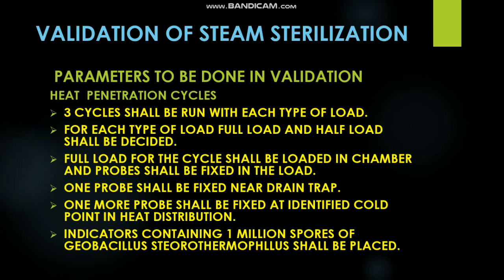After loading the steam sterilizer, probes shall be placed in the load, and 1 probe shall be placed at the point which was identified as slow to heat or cold point in our empty chamber study, and a second probe is compulsory to be placed near your drain trap. Then after doing all these things, biological indicators having a minimum population of 1 million spores shall be loaded along with the temperature probes.